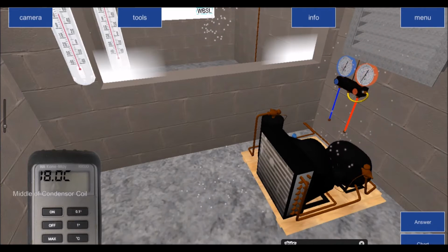And this is where we have to have the knowledge and know for a fact that for an air-cooled condenser, doesn't matter what size it is, doesn't matter how big it is, manufacturers have designed them to operate with a delta T total of between 10 and 20 degrees of a difference. So what that means is that if I've got air coming on at 20 degrees, my condensing temperature needs to be a minimum of 10 degrees higher or a maximum of 20 degrees higher than the air-on temperature. So the lowest condensing temperature that I should have should be 30 degrees, and the highest should be 40 degrees.